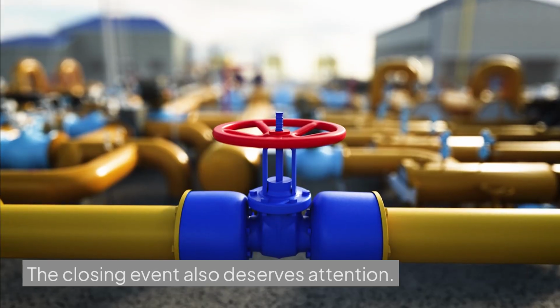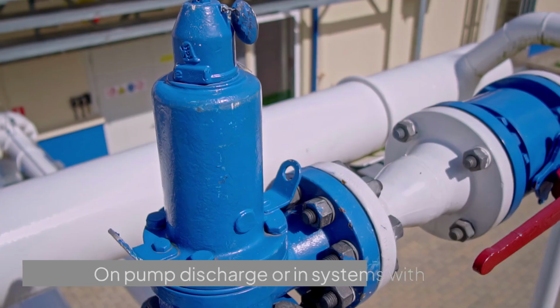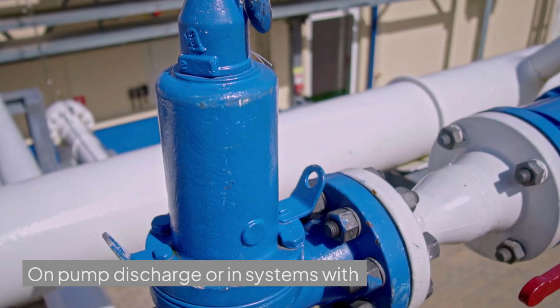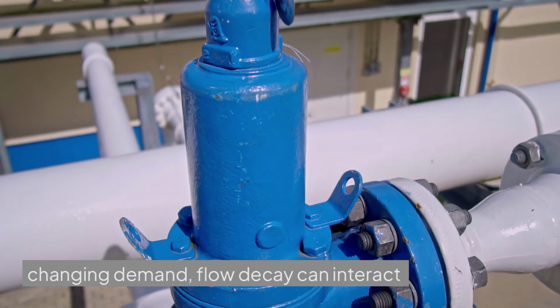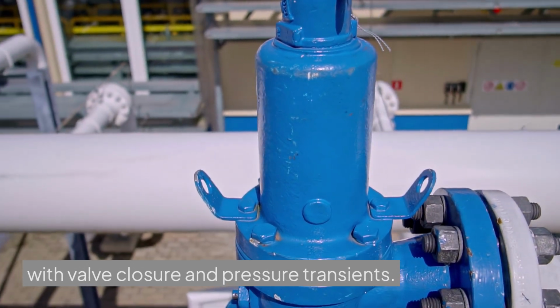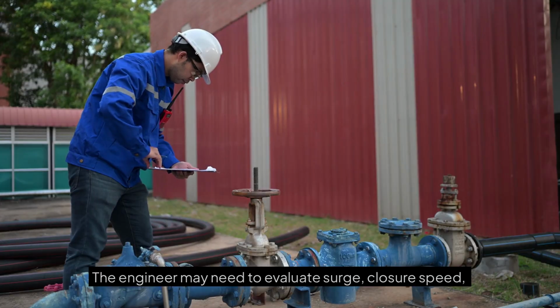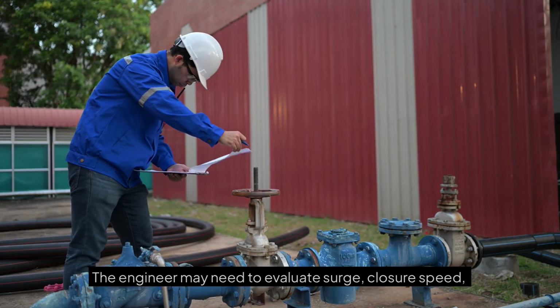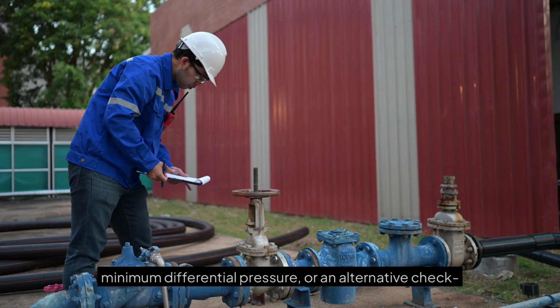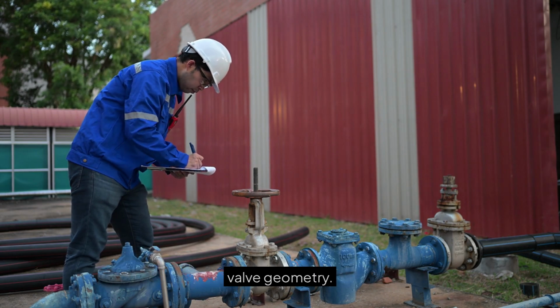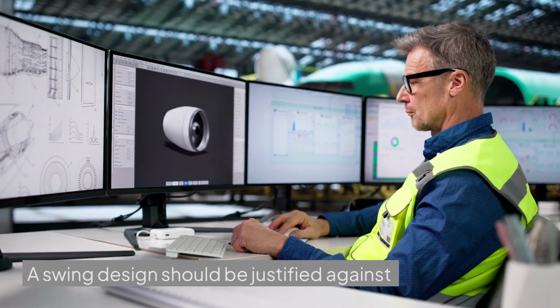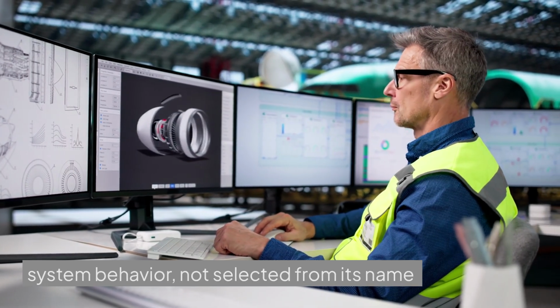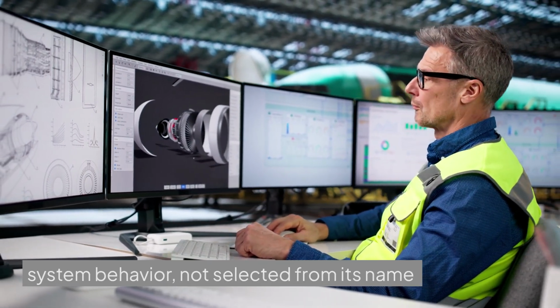The closing event also deserves attention. On pump discharge or in systems with changing demand, flow decay can interact with valve closure and pressure transients. The engineer may need to evaluate surge, closure speed, minimum differential pressure, or an alternative check valve geometry. A swing design should be justified against system behavior, not selected from its name alone.